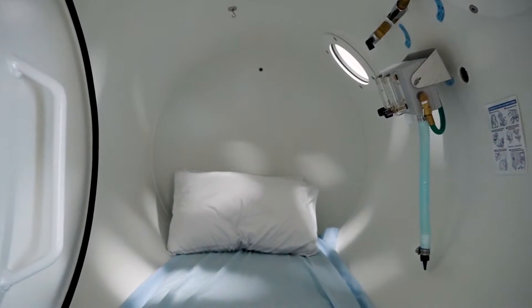The third piece is the cleanliness of the physical equipment. With every session, the pillowcases are changed, the mattress sheets are changed, and the chamber is wiped down. In our office, we use a mixture of hydrogen peroxide, and as we know, hydrogen peroxide virtually kills everything. We don't like to use harsh chemicals or chemicals with strong odors, primarily because in the chamber environment, you will absorb everything inside at higher rates due to the pressure. So we want to use very clean, very pure, and very safe chemicals. Hydrogen peroxide is a very safe cleaning tool — it doesn't leave any residual coating and doesn't destroy materials on either a soft or hard chamber.